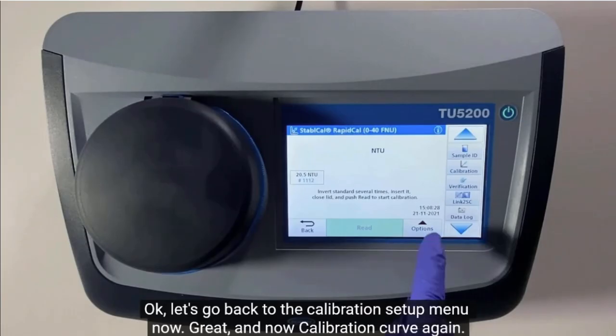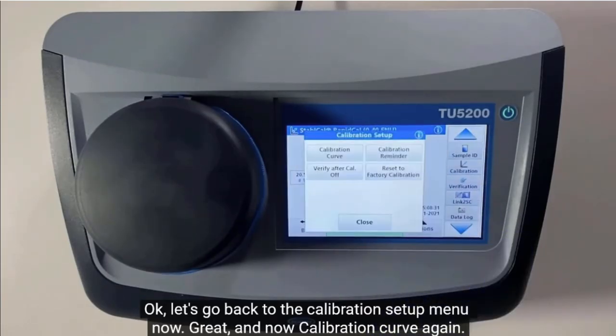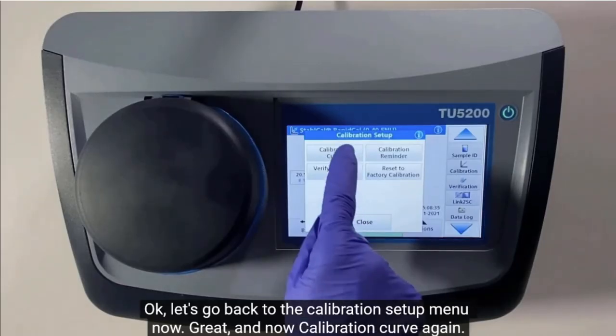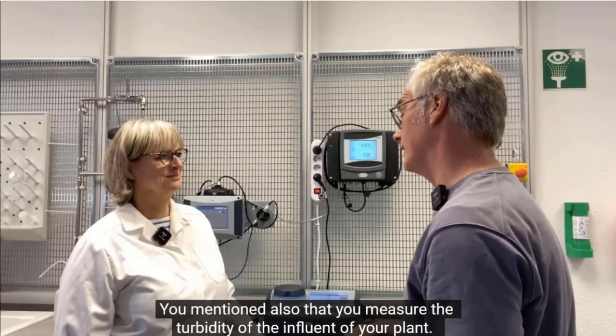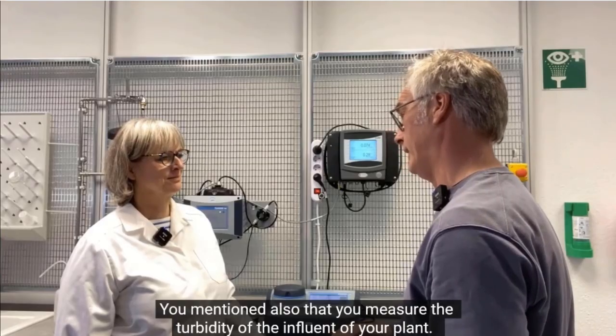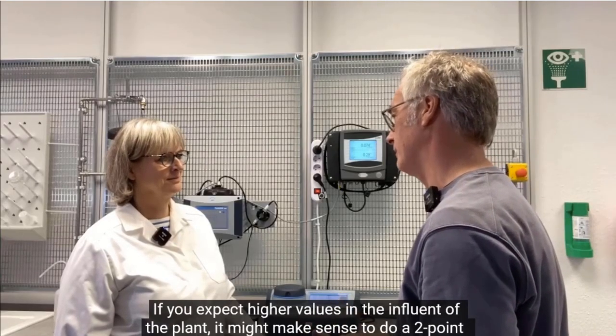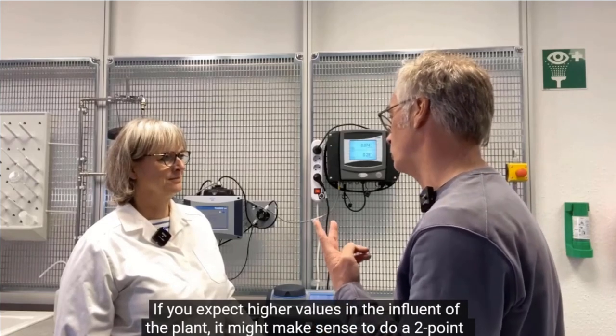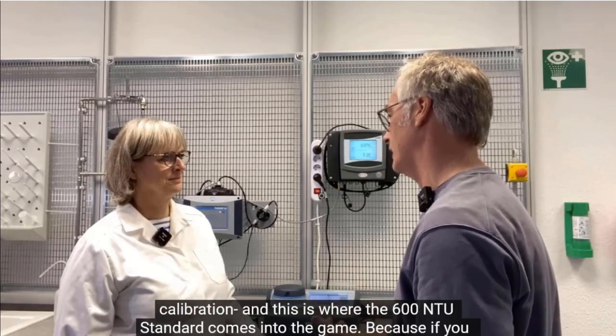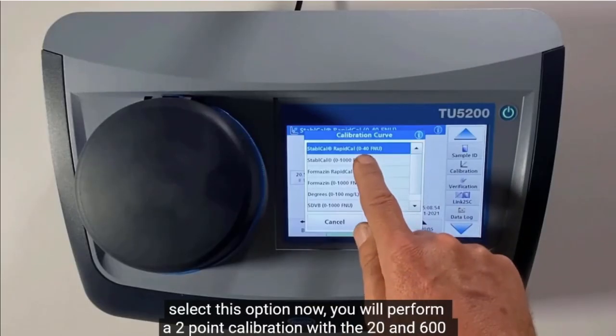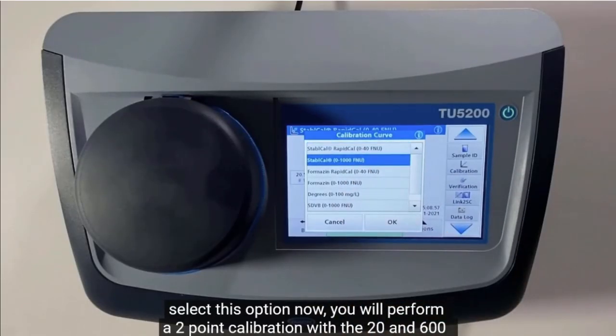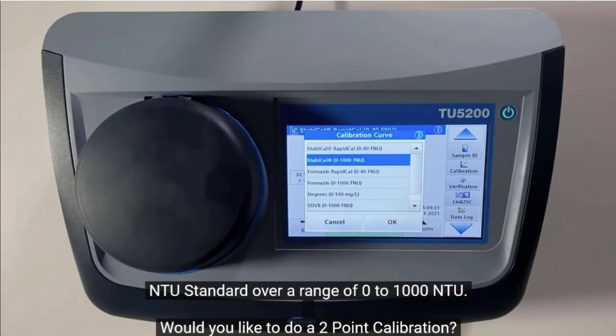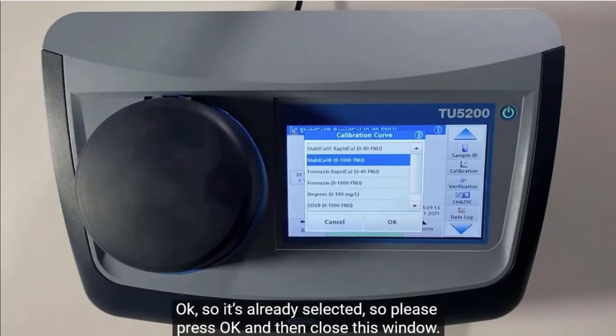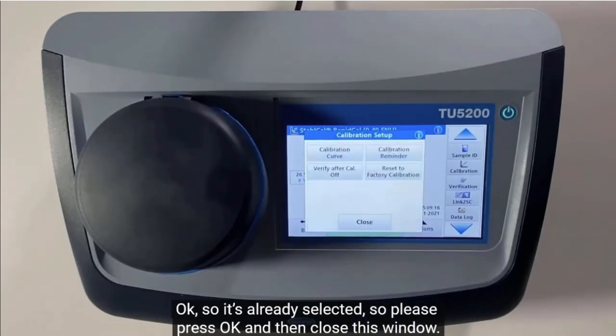Okay, let's go back to the calibration setup menu now. Great, and now calibration curve again. You mentioned also that you measure the turbidity of the influent of your plant. So if you expect higher values in the influent of a plant, it might make sense to do a two-point calibration. And this is where the 600 NTU standard comes into the game. Because if you select this option now, you will perform a two-point calibration with the 20 and 600 NTU standard over a range of 0 to 1000 NTU. Would you like to do a two-point calibration? Yeah, why not? Okay, so it's already selected, so please press OK and then close this window.